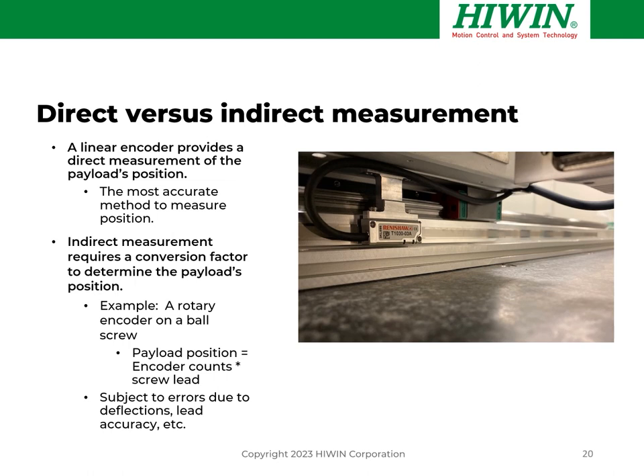Encoders can be either incremental or absolute — accuracy is not really related to which type it is. Incremental encoders are the most common; they provide relative motion from a defined starting point or datum and require initialization, often called homing, upon startup. Common terms include A-quad-B encoder, TTL, or square wave. Absolute encoders provide a direct reading of position using a digital word protocol — homing isn't needed, as the encoder knows its position immediately upon power-up. Common absolute encoder protocols include EnDat and BiSS. It's important to verify that the servo drive supports the encoder protocol to ensure compatibility.